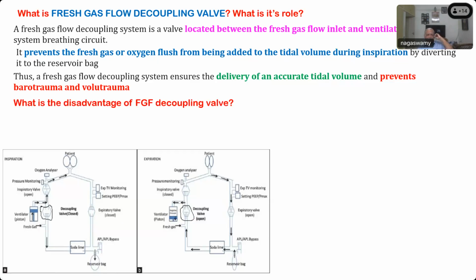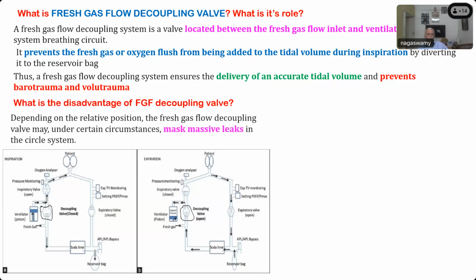What is the disadvantage of having this decoupling valve in the machine? It is present only in Draeger machines, not in all machines. What is the disadvantage? Why do not all machines include this? Depending upon the relative position, the fresh gas flow decoupling valve may under some circumstances mask any massive leaks in the system. Okay, so that is the disadvantage. What are the ways the preset tidal volume is delivered accurately in a Draeger machine?